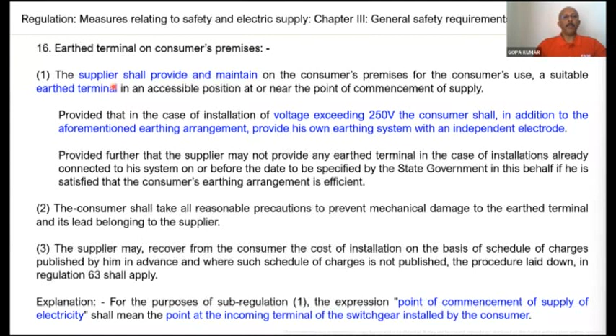The meaning is: you have a transformer - imagine this is for public electricity distribution. The transformer is the source. You have the distribution, and finally the origin of installation - that's the point of commencement of supply. You can see a PE conductor - this is the earth wire starting from the transformer neutral up to every consumer premise.